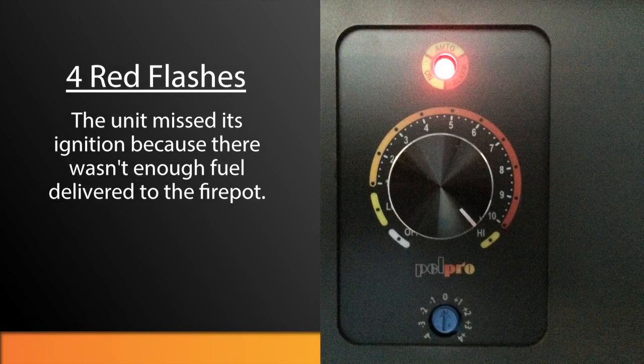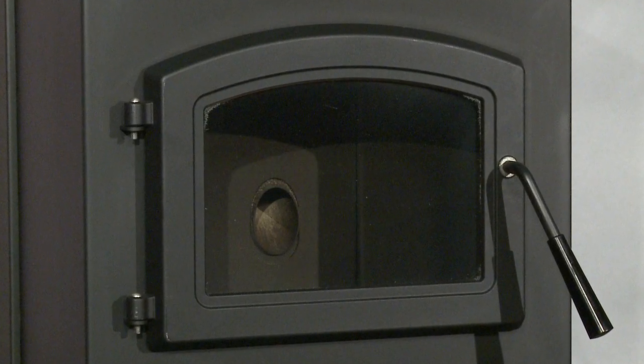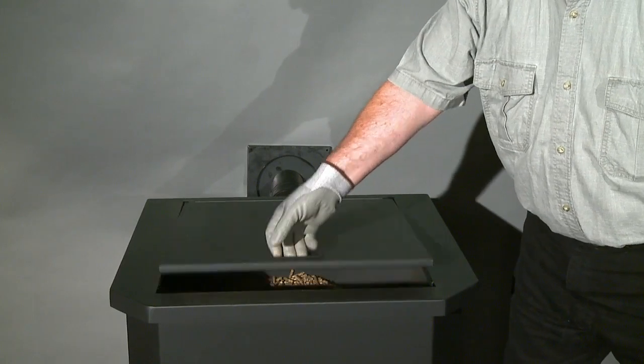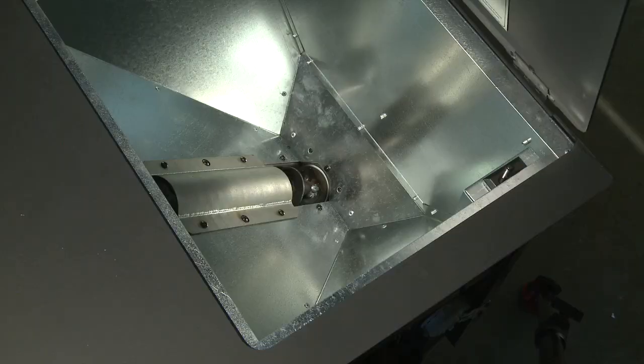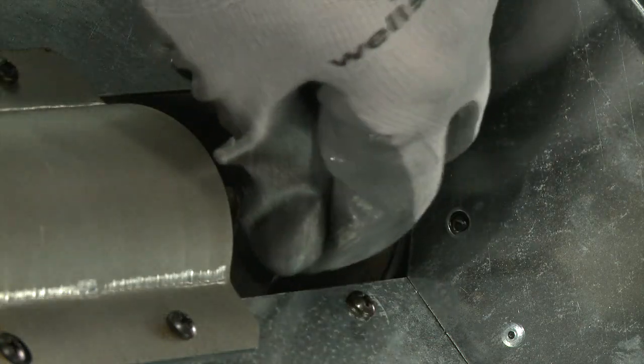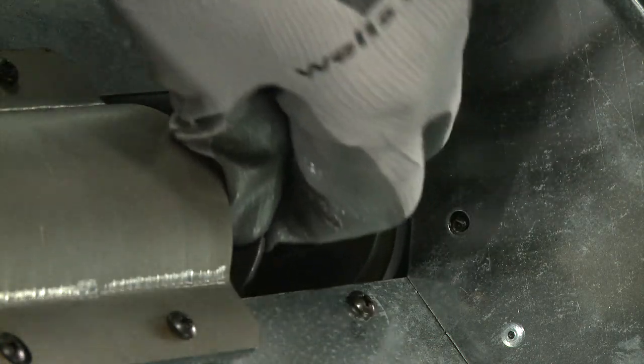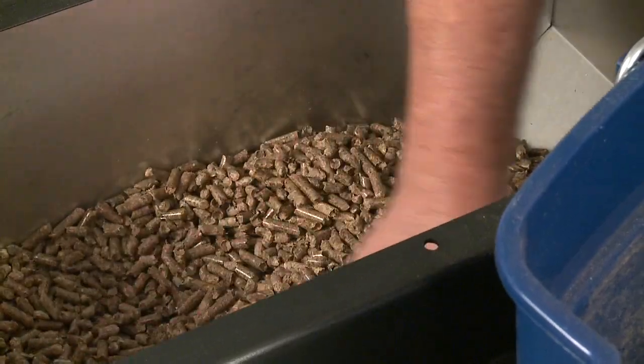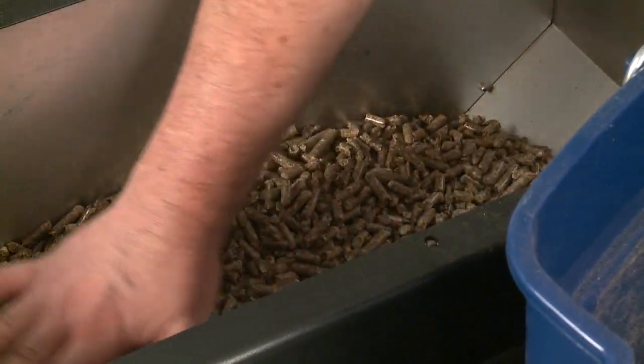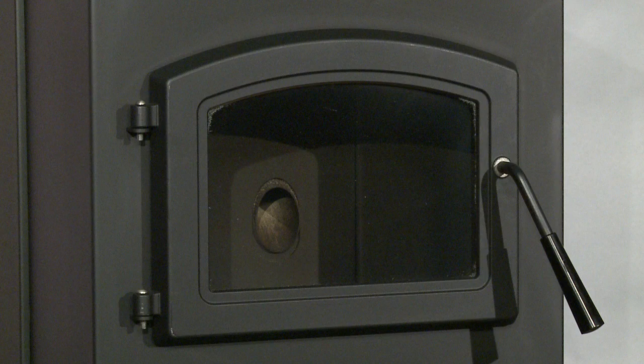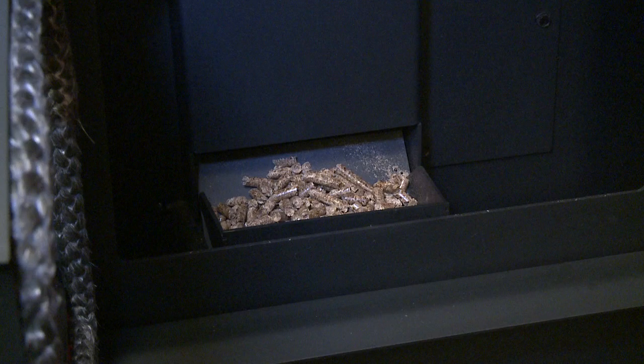4 red flashes means the unit missed its ignition because there wasn't enough fuel delivered to the fire pot. This can happen for several reasons. First, make sure there are pellets in the hopper. If pellets are already in the hopper, confirm that the auger isn't jammed and is able to turn properly. If the unit has pellets in the hopper and no auger jams, it may mean that the fire pot is too dirty for the pellets to get near enough to the ignition hole in the fire pot.